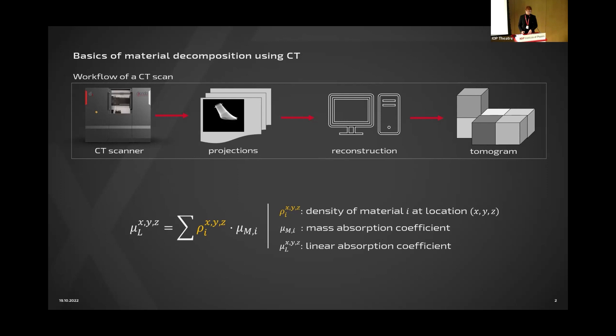Each voxel contains information of this linear absorption coefficient μ^(x,y,z), which consists of density ρ and mass attenuation coefficient μ_m. In case you have one material inside your workpiece and you know this μ_m and you measure μ_l, you directly get the density.